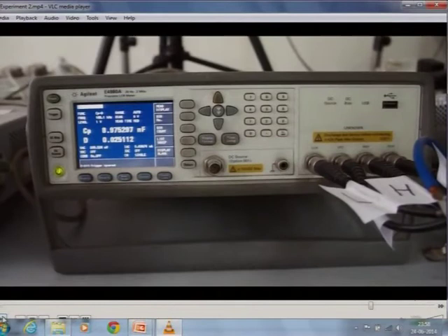This instrument is called LCR, and it is used for the experiments which are based on the EMI technique. It captures the conductance and the susceptance signatures of the PZT patch, and this LCR meter is also connected to the user's computer via internet through vPro software. So, in this experiment also you need vPro software to perform the experiment.